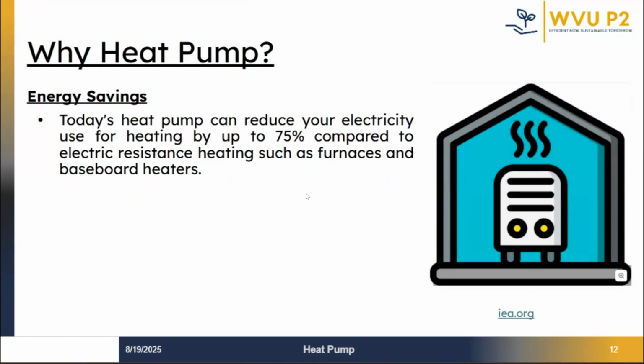Because most of the heat is transferred rather than generated, heat pumps are far more efficient than conventional heating technologies such as boilers and heaters, and can be cheaper to run. The output of energy in the form of heat is normally several times greater than the power required to run the heat pump, normally in the form of electricity. A modern heat pump can cut our heating electricity use by up to 75% compared to an old-school electric furnace or baseboard heaters. It has other advantages: it can lower the monthly bills, it is more efficient and comfortable year round, and it generates less waste, which is also a greener policy.